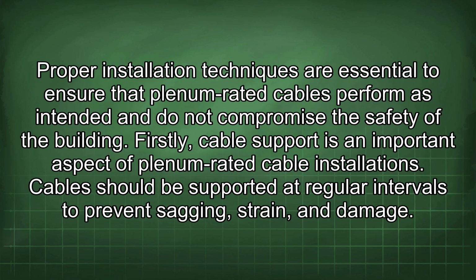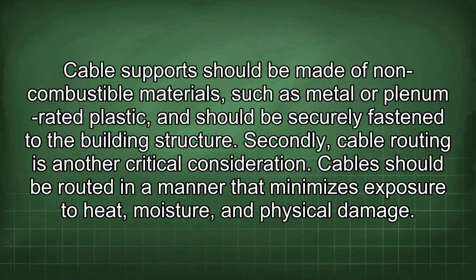Proper installation techniques are essential to ensure that plenum-rated cables perform as intended and do not compromise the safety of the building. Firstly, cable support is an important aspect of plenum-rated cable installations. Cables should be supported at regular intervals to prevent sagging, strain, and damage. Cable support should be made of non-combustible materials such as metal or plenum-rated plastic and should be securely fastened to the building structure. Secondly, cable routing is another critical consideration.